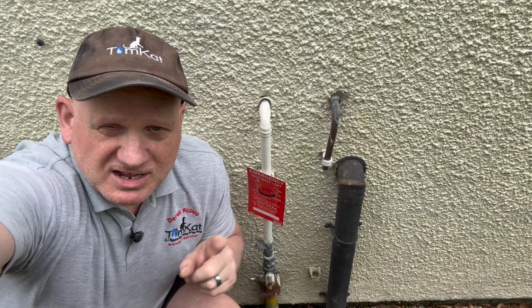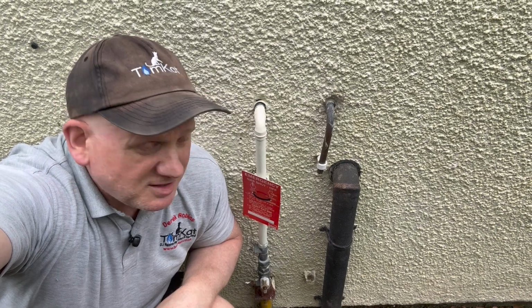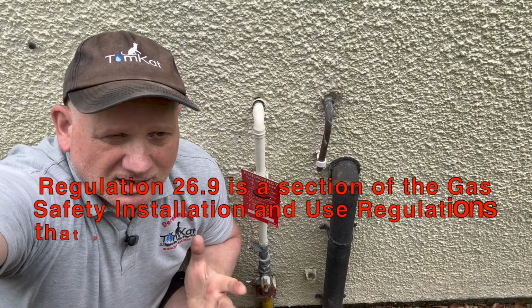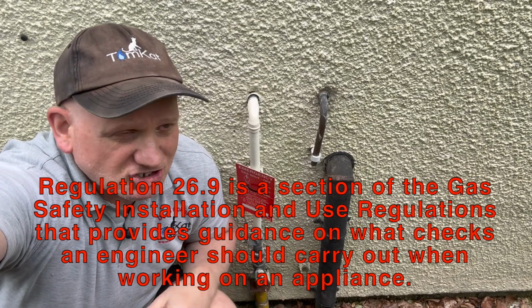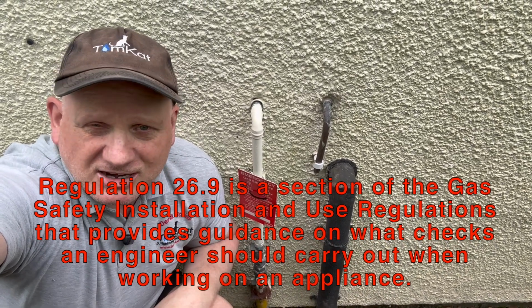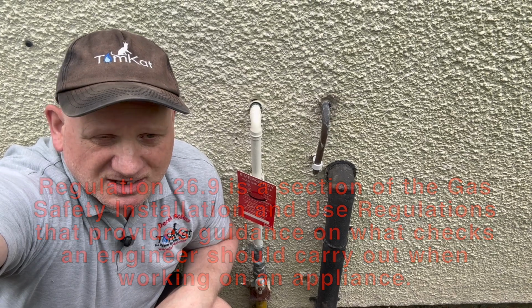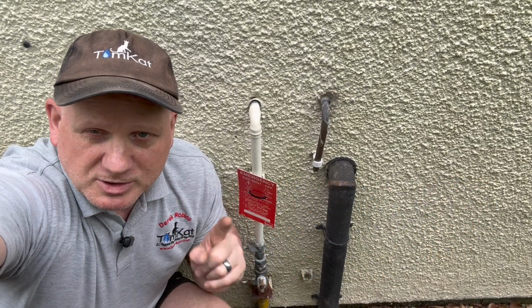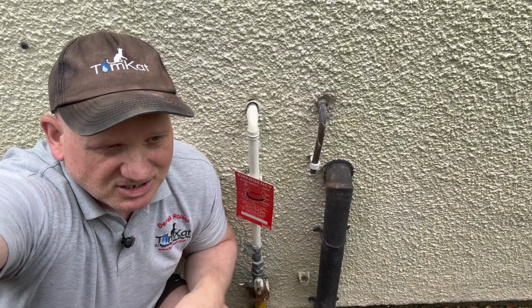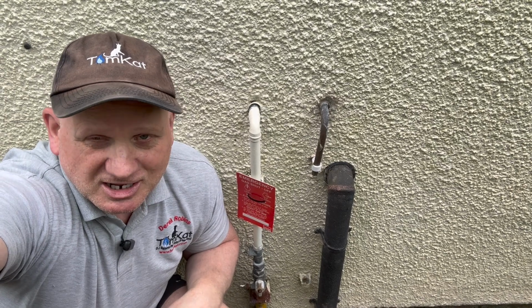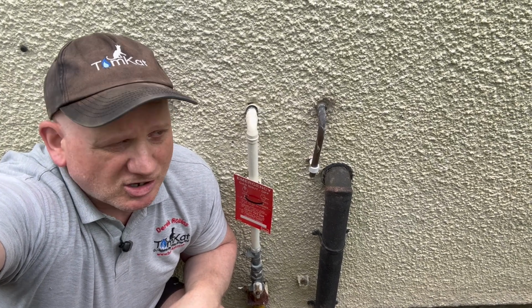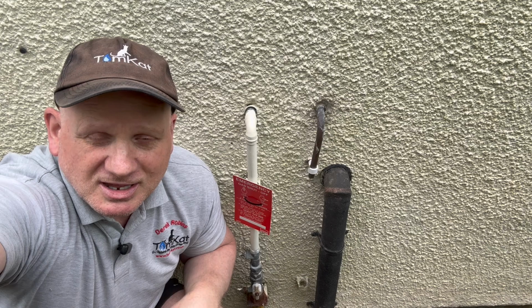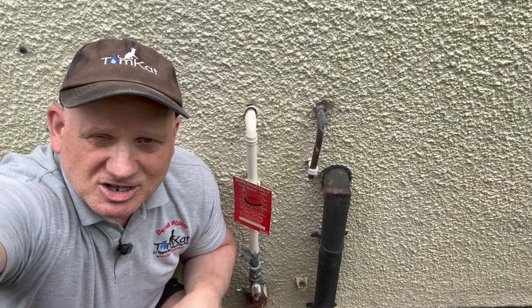Now, on a service, do we have to do a tightness test? Well, regulation 26.9 of the Gas Safety Installation and Use Regulations says we don't need to do a tightness test when we're doing a service. But I will be doing a tightness test on this installation, but I won't be using it in this video. You'll have to look out for the LPG videos. Anyway, let's get on with this service.